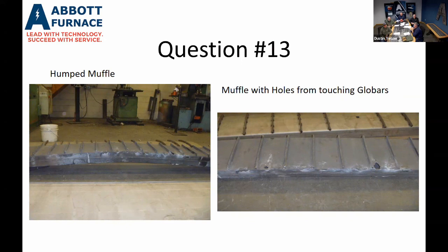So basically they ramped that muffle from 0 degrees to 2000 degrees in a matter of hours. They bowed it up, and it bowed so bad, if you can kind of see on the second picture, the holes burned in the top of the muffle and on the side there. Those are from the glow bars of the heating elements, where the muffle grew up and actually hit the heating elements and burnt those holes in it.